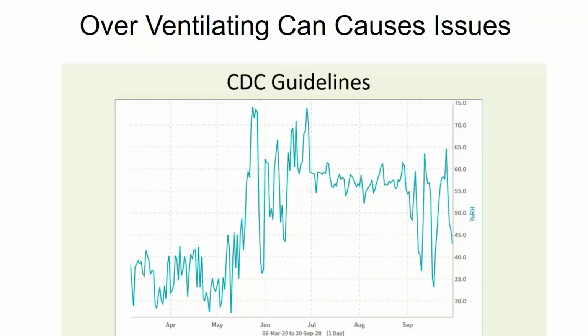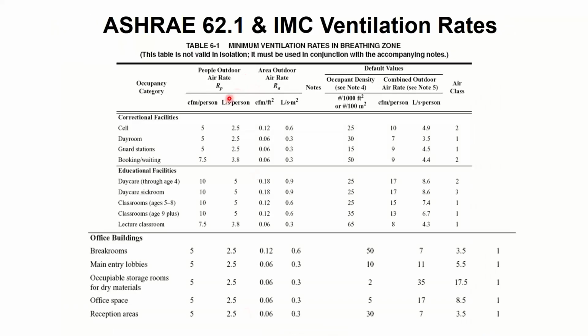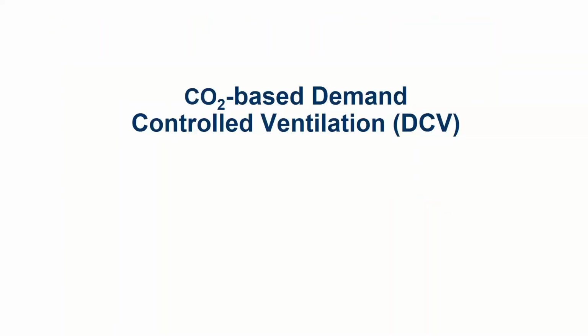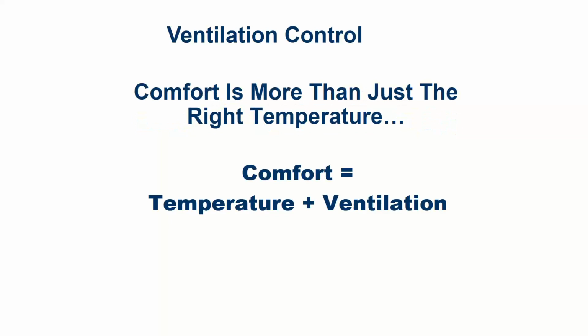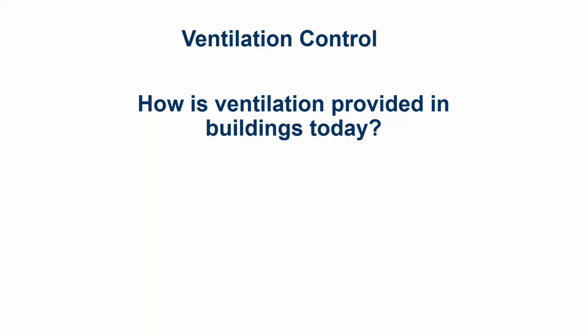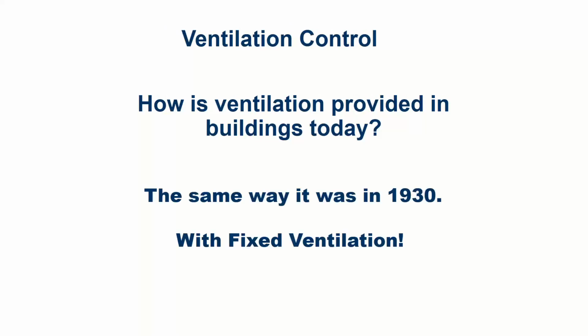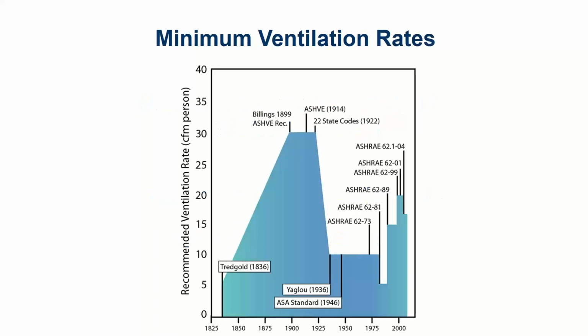Yeah, I absolutely can. And the entire and only reason that in the codes we split this into 2 numbers and made you do the math was so we can do demand control ventilation. That is literally the reason why. So what demand control ventilation does is it takes into effect the concept that we control the temperature in a space historically, but we don't control the ventilation. It's just like on off, you're there, you're not there kind of thing. So what we want to do is actually measure the ventilation in the space and control to that ventilation rate.